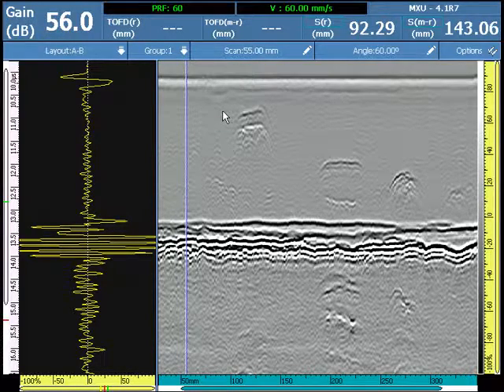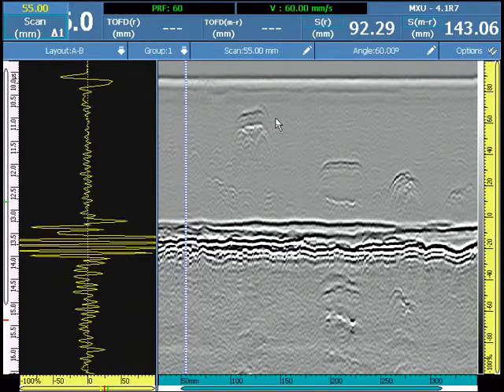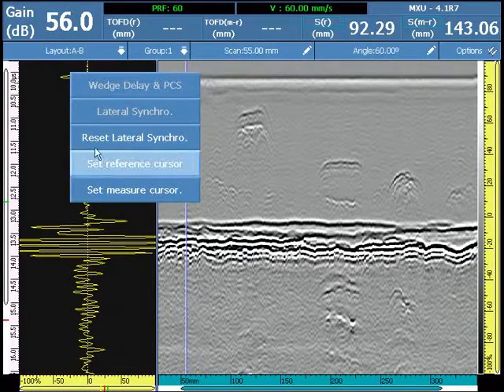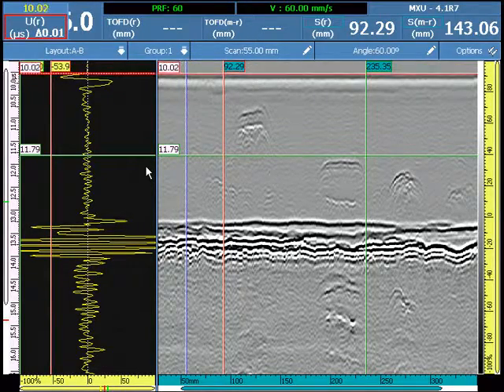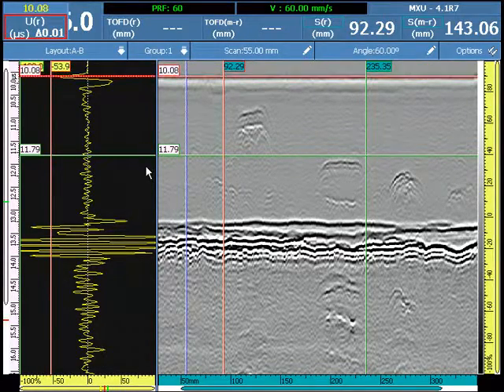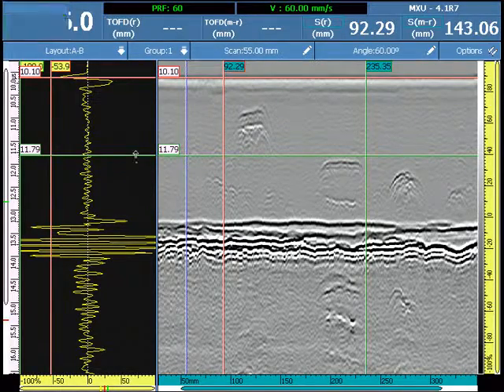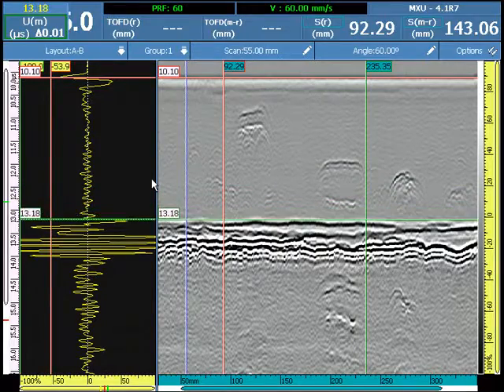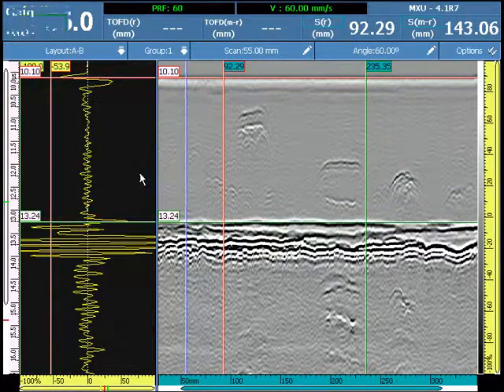Prior to placing the cursors, we are going to set a reference A-scan representative of the inspection, and set the position of the reference cursor on the first peak of the lateral wave, and set the position of the measure cursor on the first peak in opposite phase of the back wall.